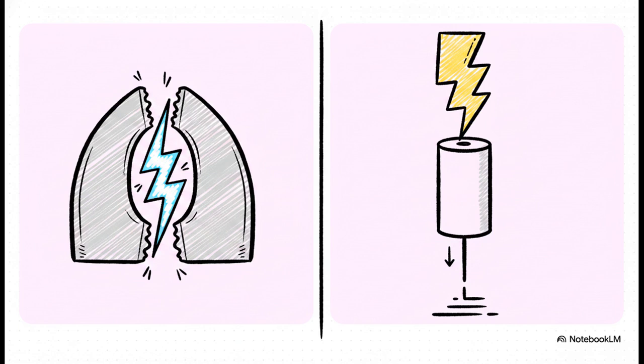But on the other hand, we have surge arresters which do the exact same job, but with incredible precision. A surge arrester uses a metal oxide varistor. At normal operating voltages, it acts just like an open circuit, totally invisible to the system. But the exact instant a massive voltage spike rolls in from lightning or a switching surge, it conducts hard. It clamps the spike down to a safe level and safely dumps that dangerous energy directly to ground, all before it ever touches the delicate winding insulation.